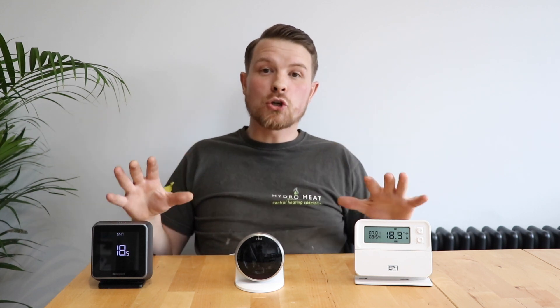That's where these smart thermostats come in, because they have a completely different way of thinking. This is where people begin to get a little bit lost, so stick with me. Let's talk about what a modulating control is. A modulating control is a control which can override and make decisions on behalf of the boiler. Previously a boiler wouldn't get any information other than 'I need some heat' — it would have a dial on the front that you'd set, and it would work to achieve that radiator temperature. Whereas with a modulating control, the thermostat uses information collected over time to decide whether to have hotter or cooler radiators.